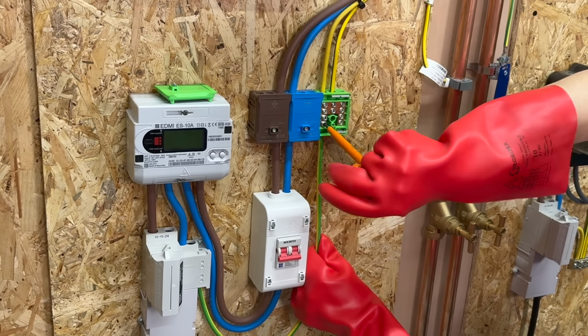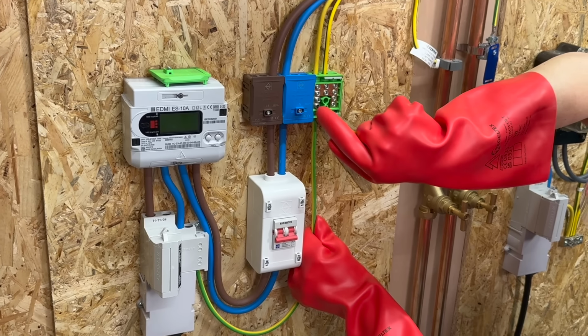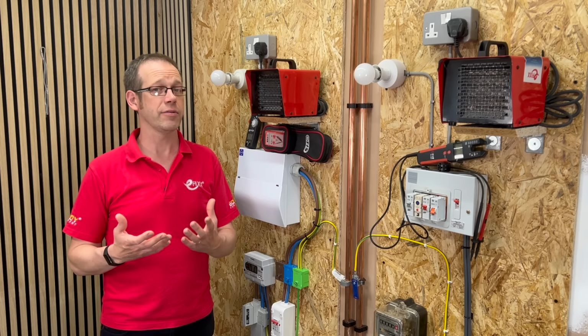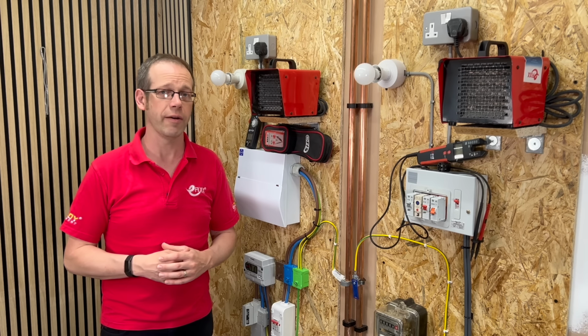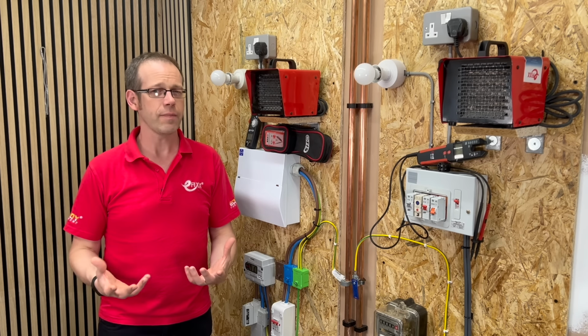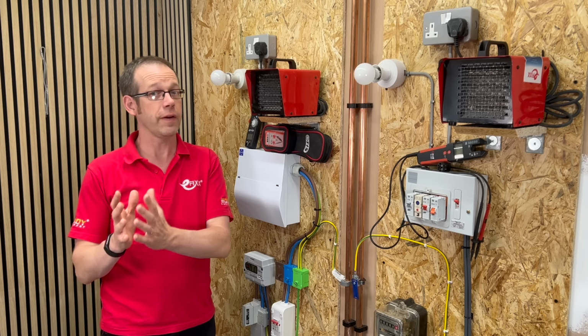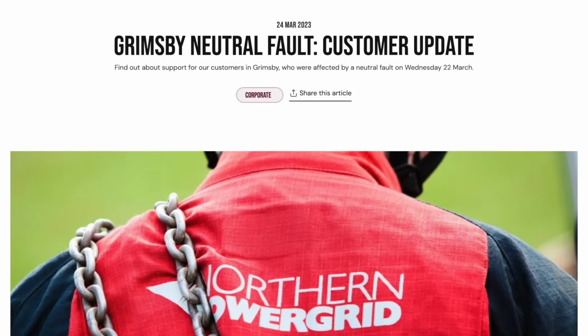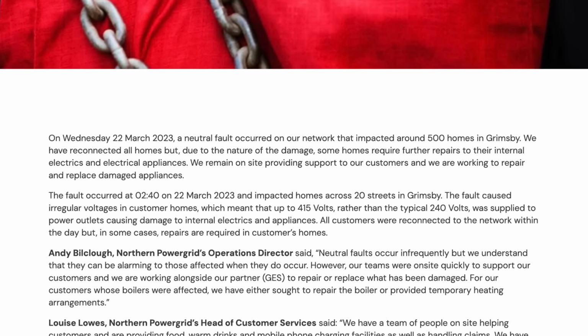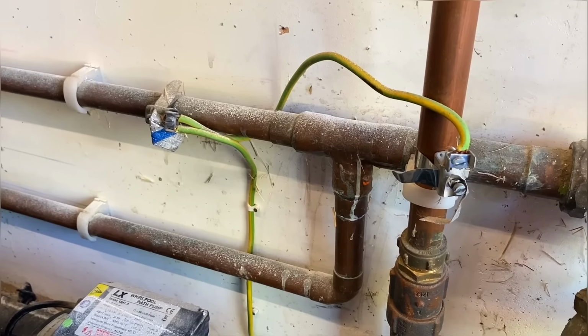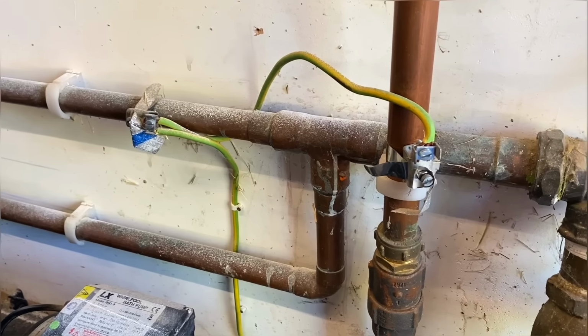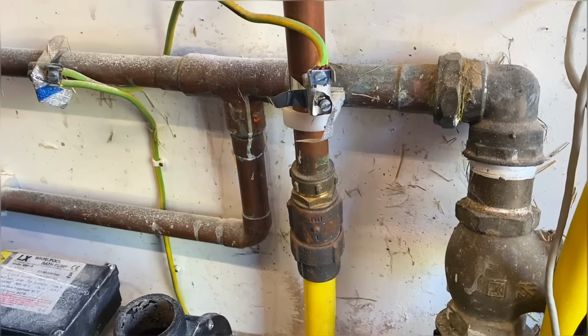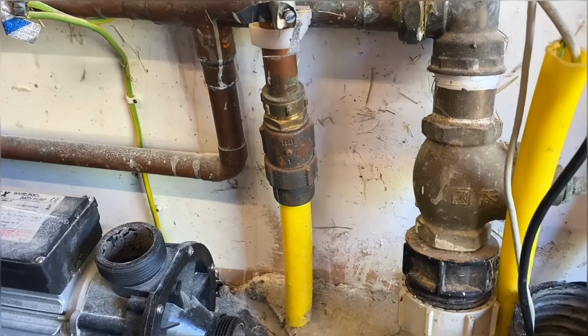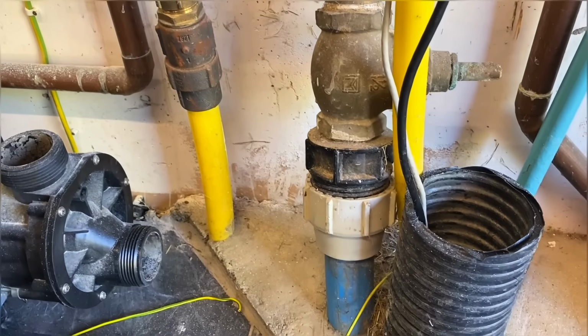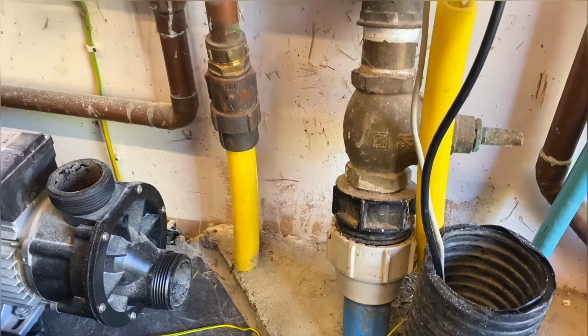So how much of a risk is this hazard? Well, it is a very real danger and it is happening out there. Currently there's around 300 of these types of faults occurring every year, so not a huge figure. However, just one of these faults can affect multiple properties. This happened in Grimsby in 2023, where a single fault affected 500 homes. But there has to be a number of factors in place for it to happen. First of all, you need to have a metallic service feeding a property. Newer installations are far more likely to have plastic water and gas pipes supplying them, and for most of these installations, the bonding in place is completely pointless.